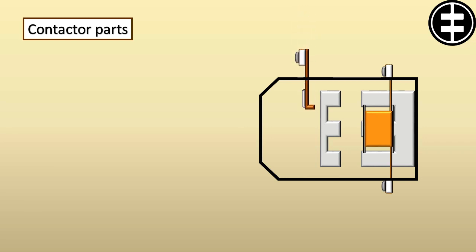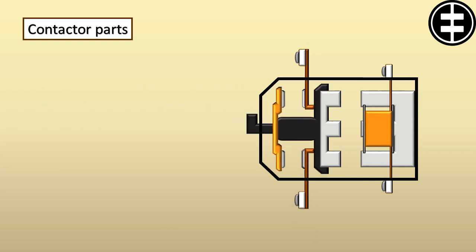Six main contacts for power connection, three are fixed, and the other three are free to move with the movable iron core. These contacts are made from pure copper, and the contact points are made from special alloy to withstand the high starting current and temperature.